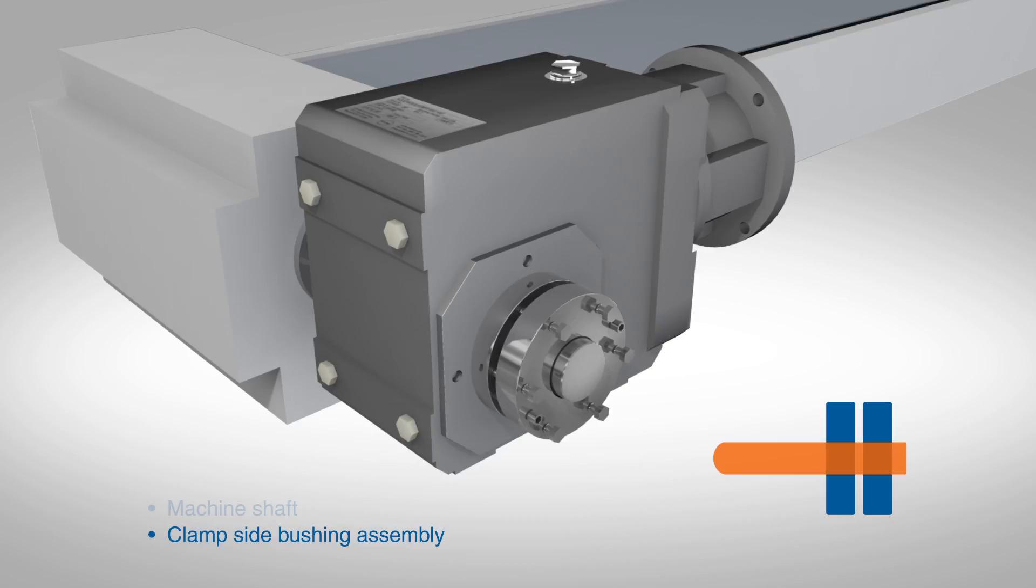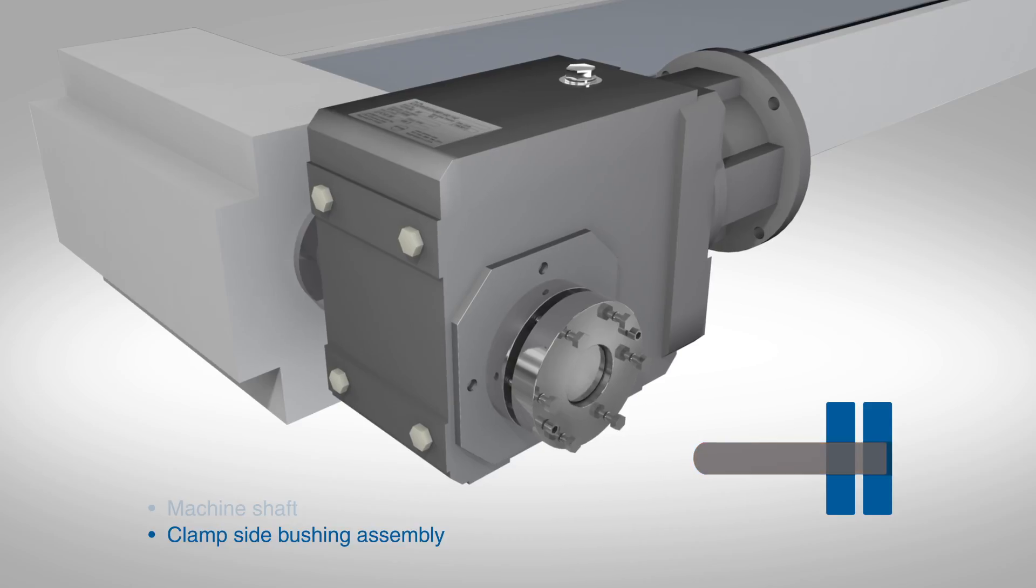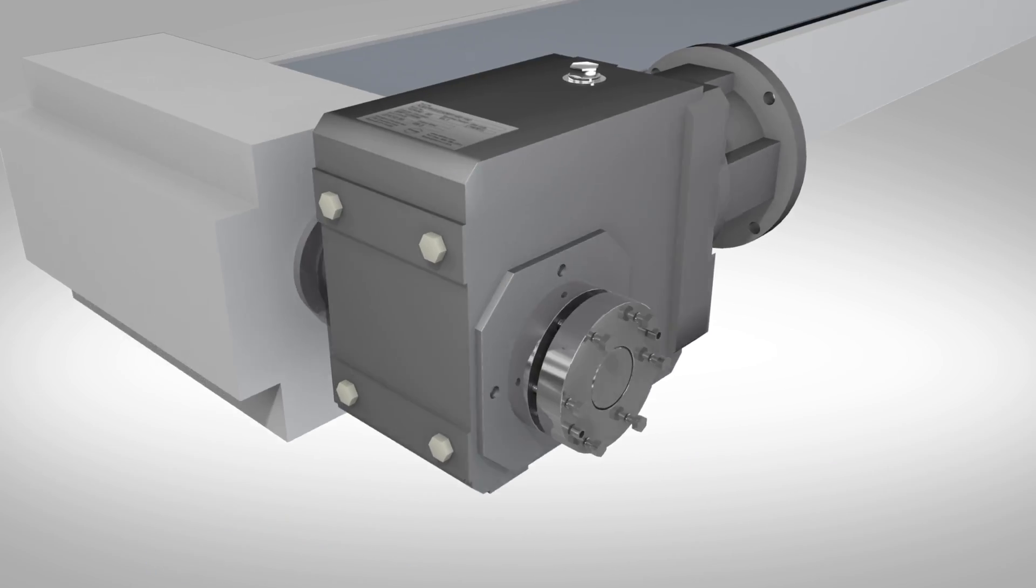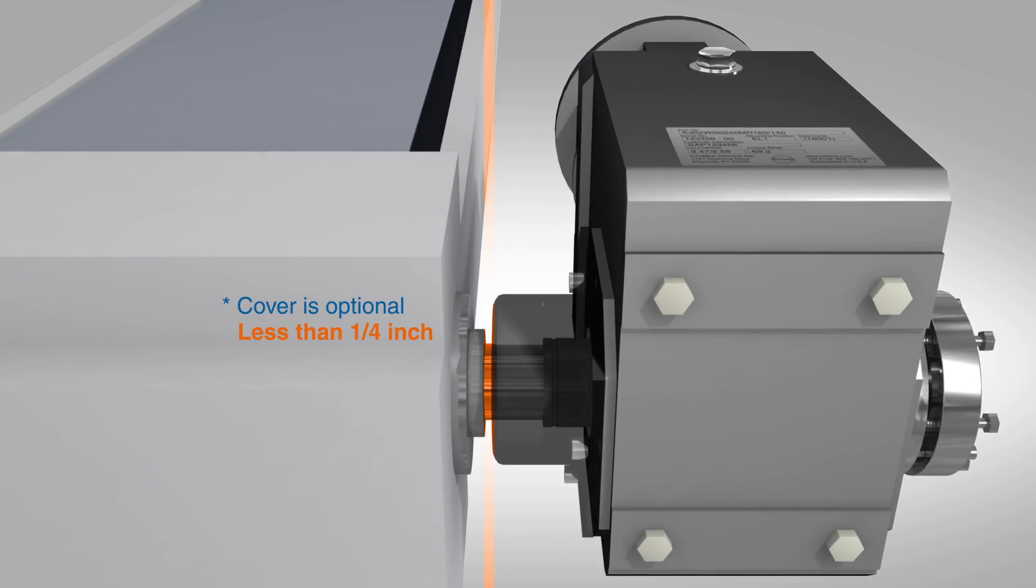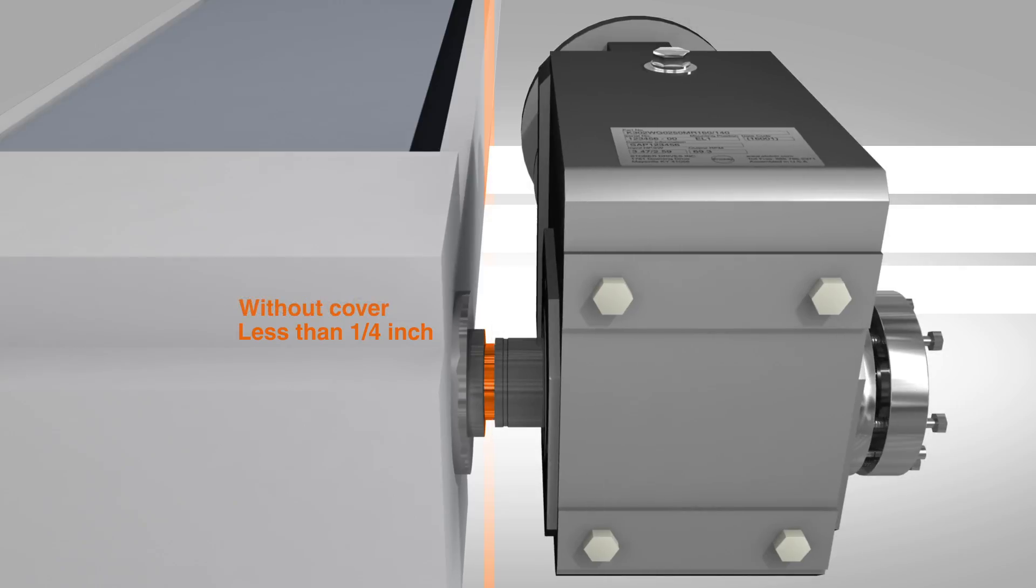Covers are optional. If the shaft does not extend completely through the bushing ring, the bushing may not clamp properly and will slip during operation. The support side should have no more than a quarter of an inch of exposed shaft between the support side covers and the equipment.